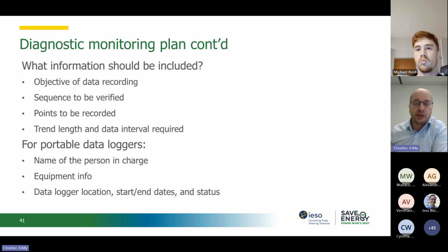Of course, a crucial element is determining which measurement points need to be tracked. Even more important, I would say, we must define the duration of recording and the frequency at which we will do it. This element is important because depending on the objective, the measurement frequency will also vary. For example, if the objective is simply to validate an operating schedule, a recording frequency every 30 minutes or 15 minutes might be more than sufficient. On the other hand, if the objective is to validate whether there's a cycling problem, more commonly known as hunting, the recording frequency may have to be every 30 seconds to be able to see it.